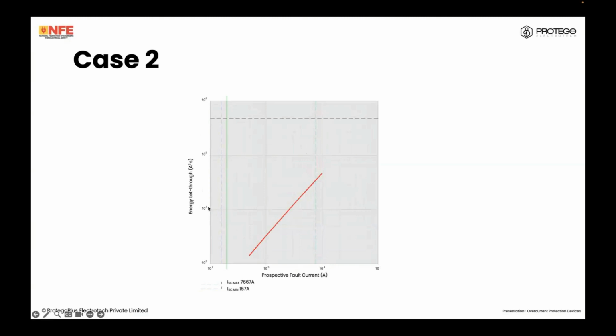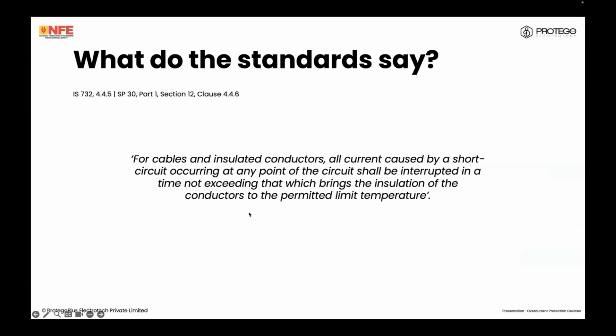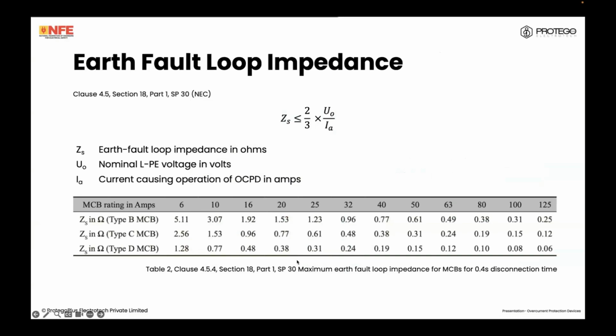This is a far more common situation where there is just not enough fault current for the device to disconnect. So if you look at this green line, this is the maximum earth fault loop impedance, and minimum current causing instantaneous operation. This is actually more than the minimum. So you can have at extremities currents between these two values where the overcurrent protection device will simply not disconnect. This is your very long cables or undersized cables. So basically, if we go back, this is not being satisfied essentially.